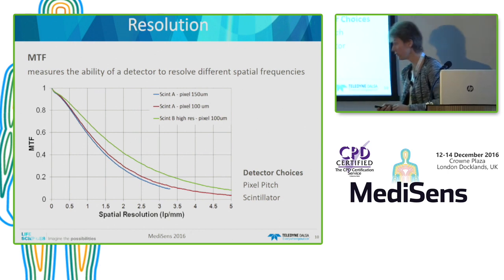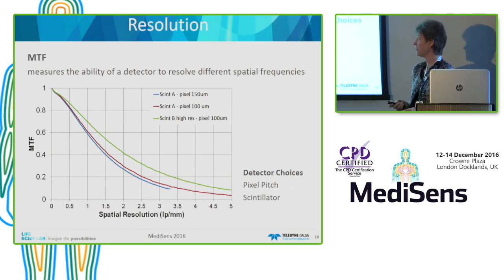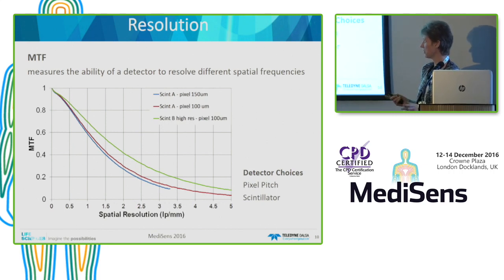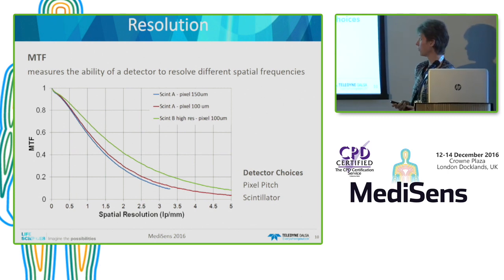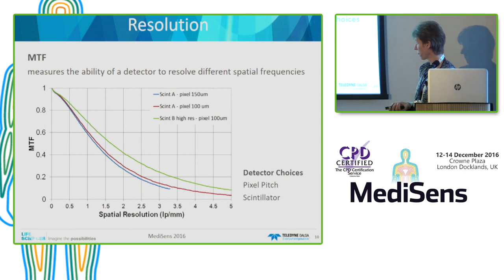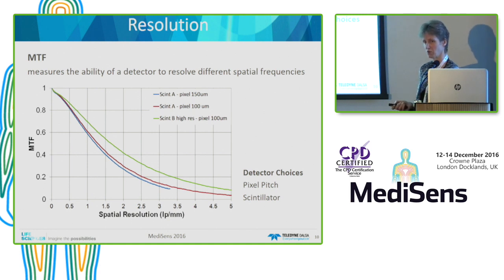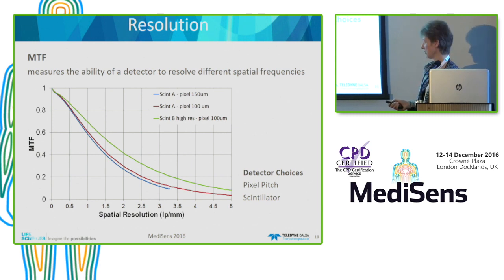Coming to resolution, MTF — the Modulation Transfer Function — measures the ability of a detector to resolve different spatial frequencies. What you see here is a difference between two detector configurations: a detector with a standard scintillator at 100 micron pixel, a detector with a standard scintillator at 150 micron pixel, and a detector with a high resolution scintillator. The high resolution scintillator clearly improves resolution considerably. There is not a big difference between the two pixel sizes — only that the Nyquist frequency is at a different point, and the curves are plotted up to the Nyquist frequency.